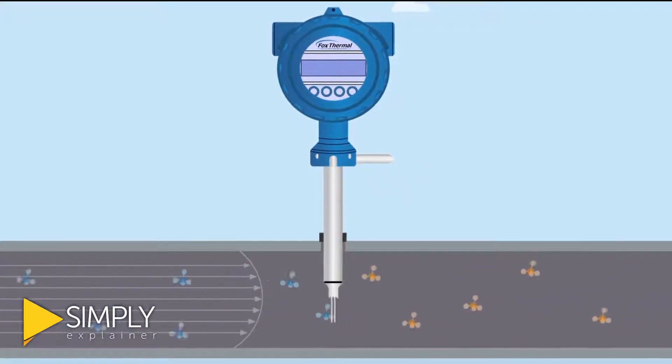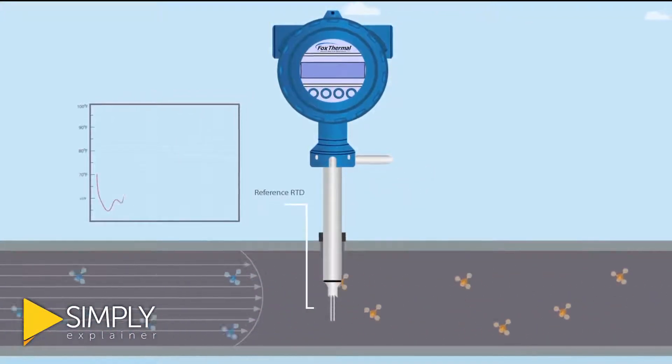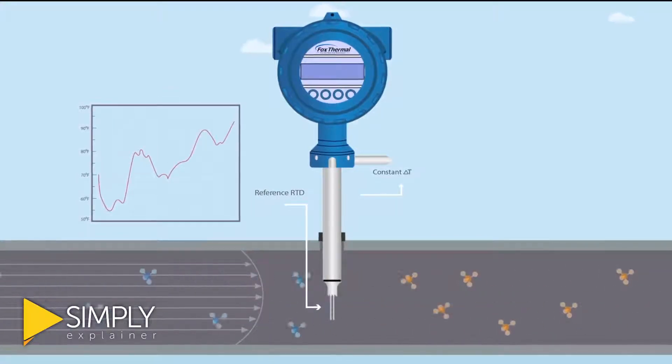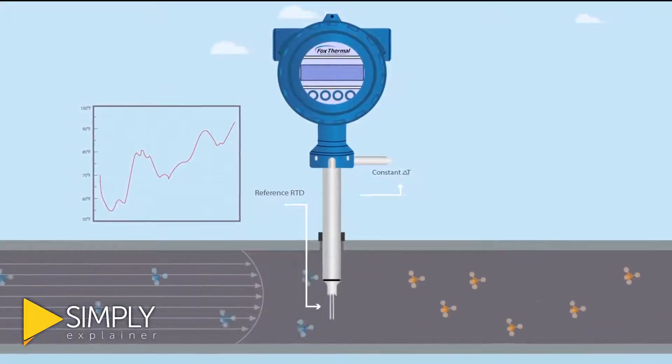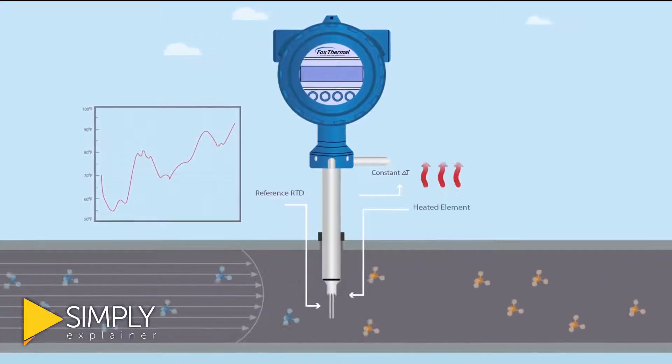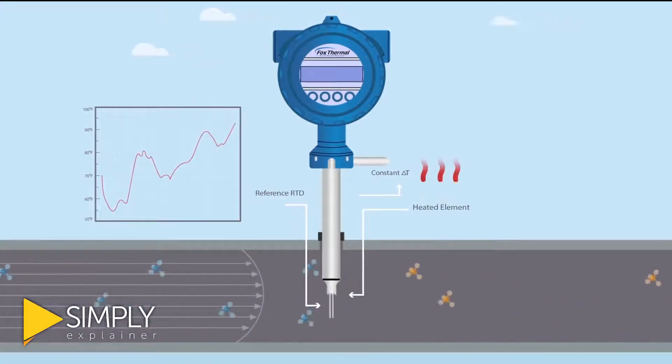Let's look at what is happening in the pipe. There are two RTD elements in contact with the flow of gas. The reference RTD measuring the gas temperature and the heated element which is kept at a constant temperature differential.